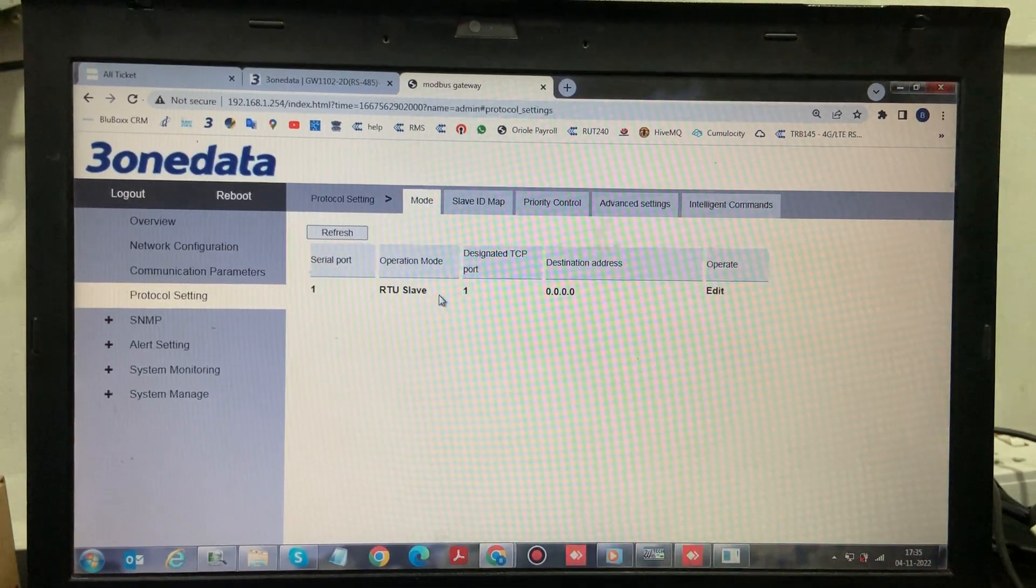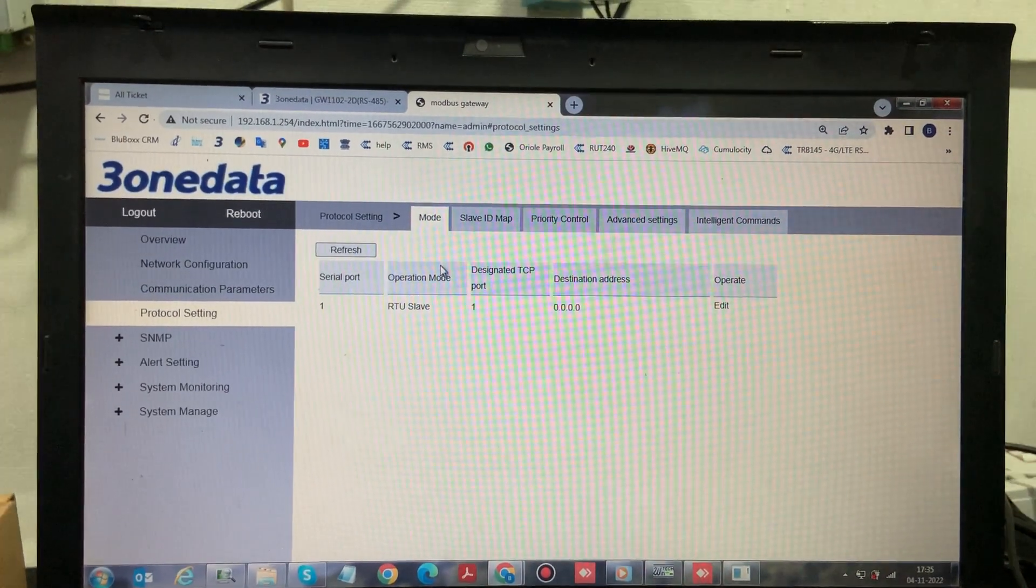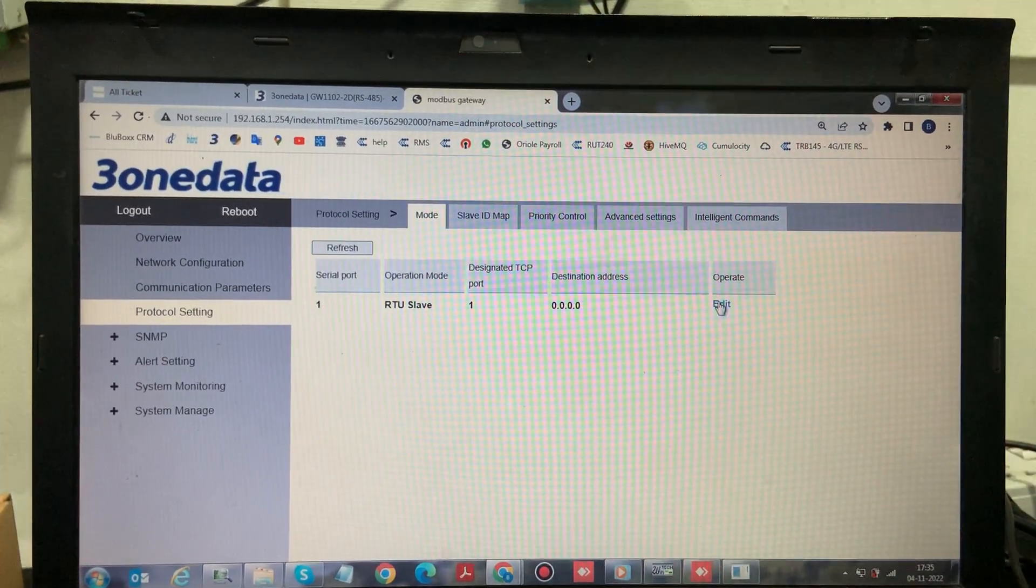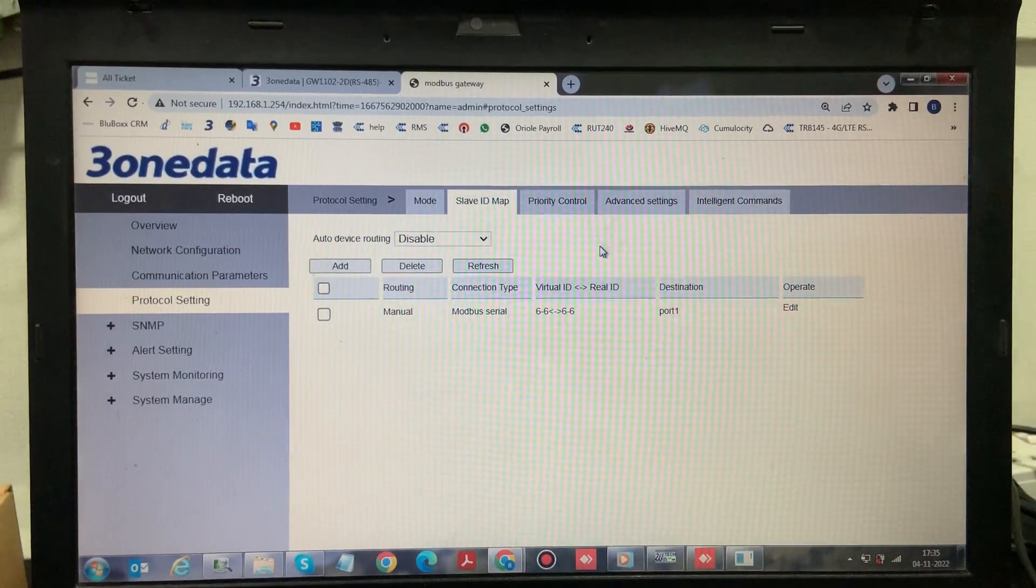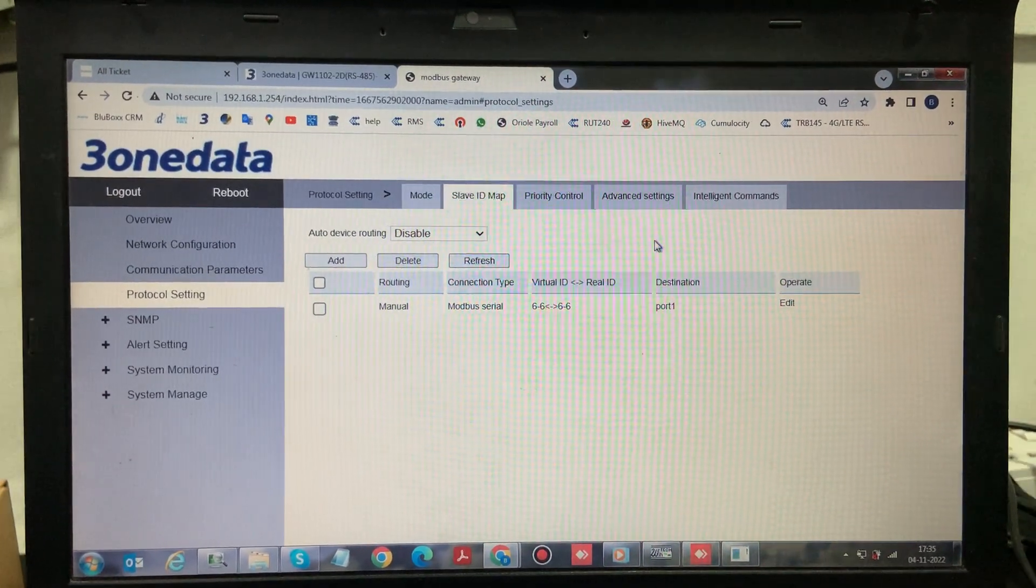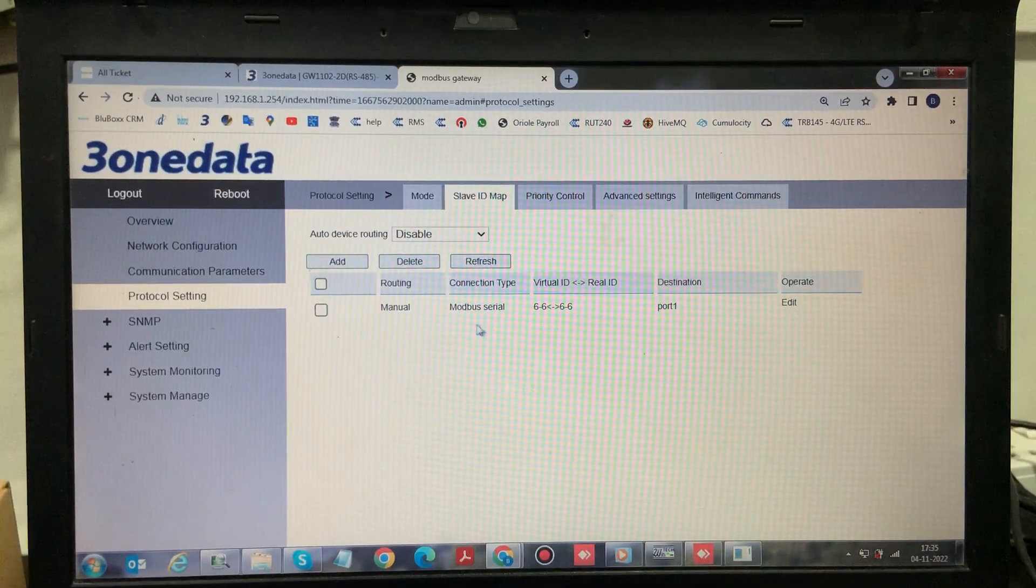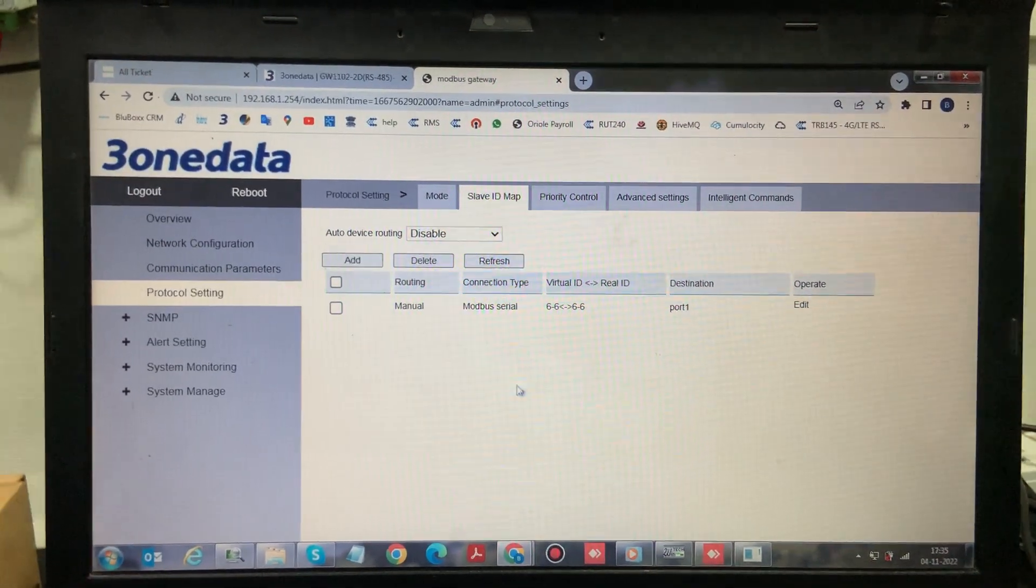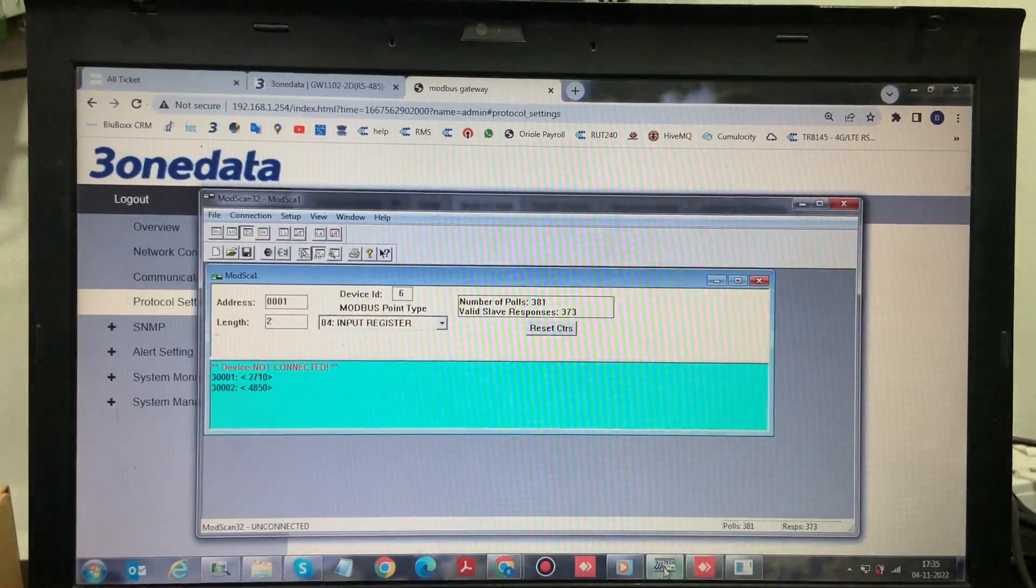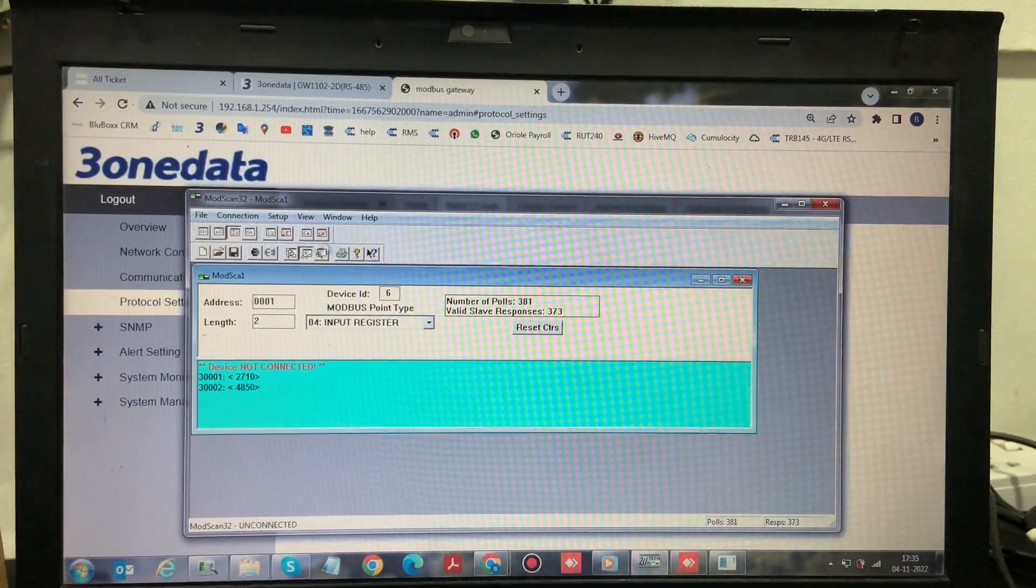After that, we need to set in the details of the slave. In slave ID mapping here, the device ID is slave number 6, so we have given the virtual ID and real ID as 6. So these are the only configurations on the converter side. Once that is done, we need to save it.